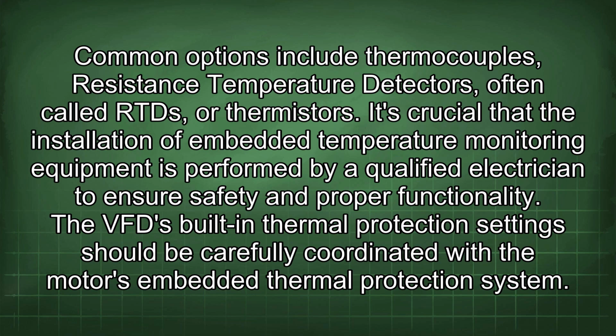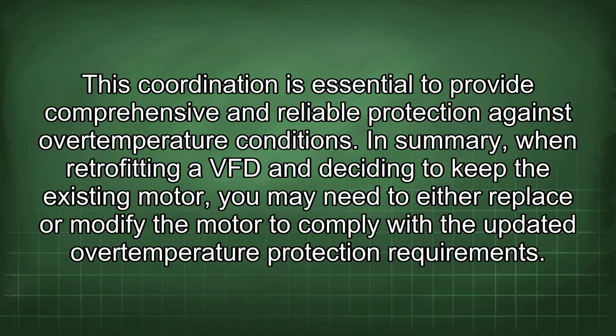It's crucial that the installation of embedded temperature monitoring equipment is performed by a qualified electrician to ensure safety and proper functionality. The VFD built-in thermal protection settings should be carefully coordinated with the motor's embedded thermal protection system. This coordination is essential to provide comprehensive and reliable protection against overtemperature conditions.